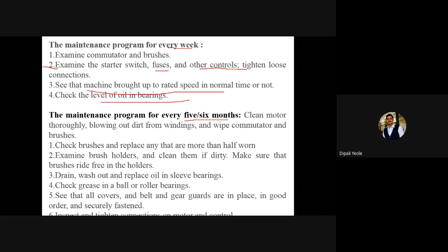Yes. Now we are interested in the maintenance for every week, and for every 5 to 6 months. So what are we going to do every week? We have to examine the commutator, the starter switch, the fuse, and the control, and see that the machine is brought up to the rated speed in normal time or not. We have to run the motor and see whether it reaches speed in normal time or not. Check the level of oil in the bearings. So this we can do every week.